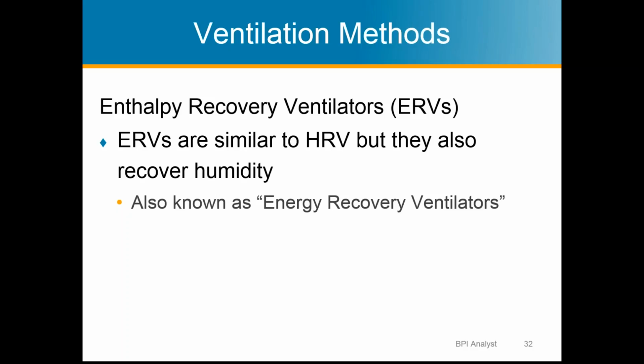So ERV is not often used in California and not necessary, but they're out there, and it's good to be aware of them. There's at least one study out there that ERVs are not as good of ventilators because, through the humidity, they can transfer VOCs back into the house when you're trying to exhaust them. So HRVs are really the way to go in most climates in California.